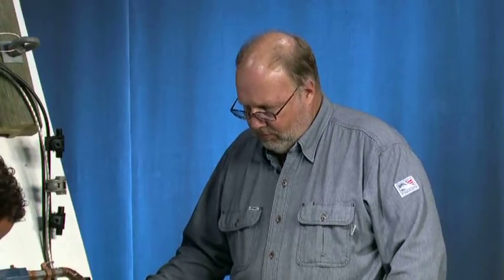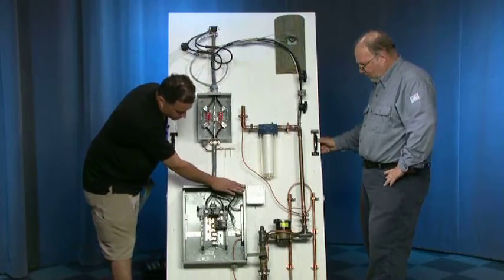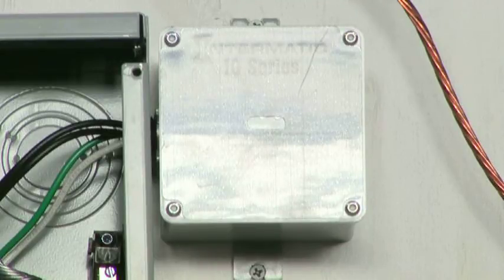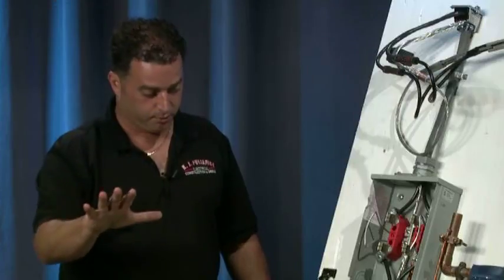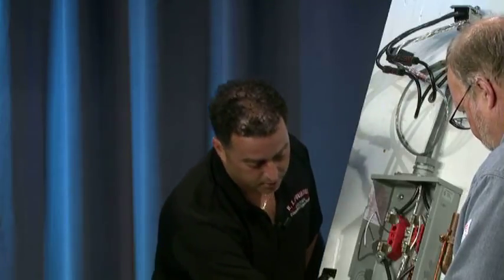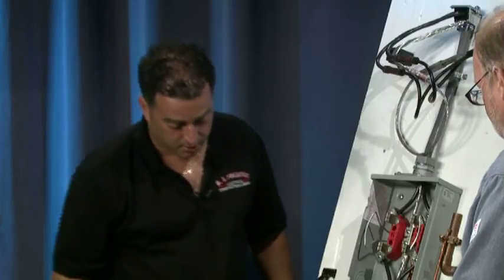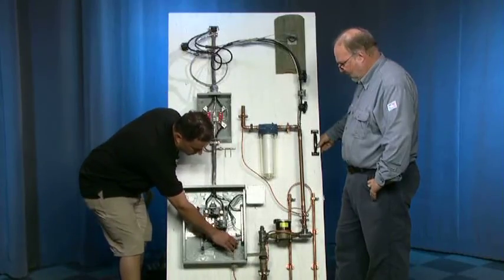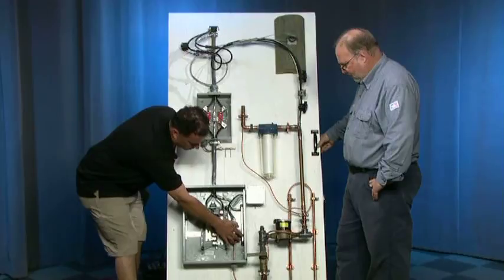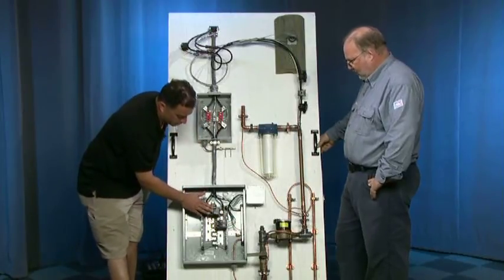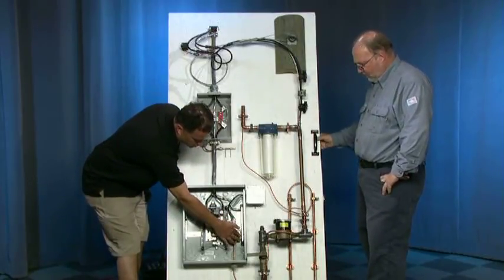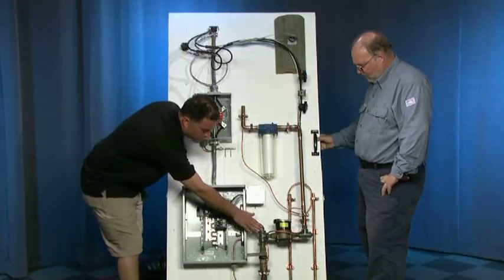This shows a whole house surge protector connected to this electrical panel via this circuit breaker. It's there for surge protection, meaning if there was an over amount of electricity going to your house, this is going to take the brunt of that to protect sensitive electronics that we all have today. This also shows the ground that leaves this panel. It's terminated with the neutral because it's a first point of disconnect. So that's where you connect your ground and your neutrals together. It goes to the water main.